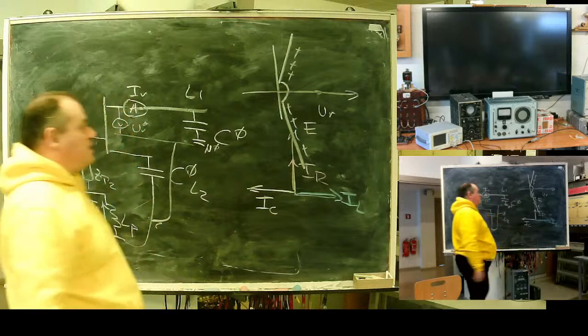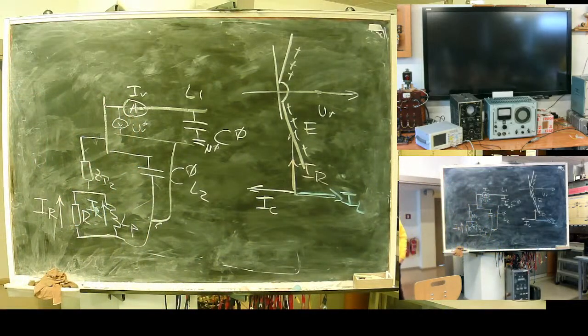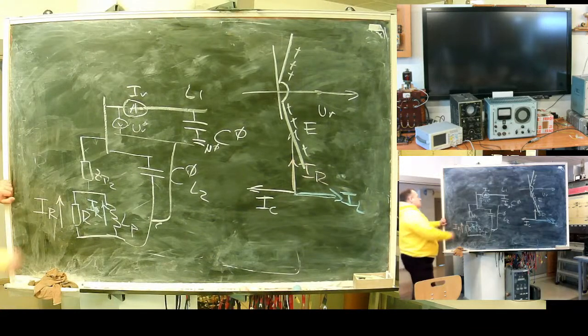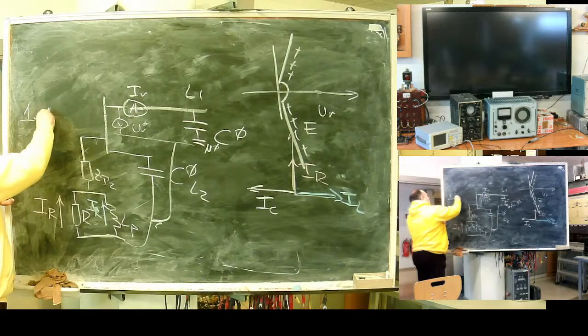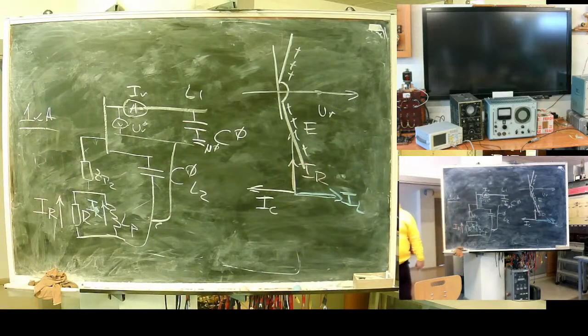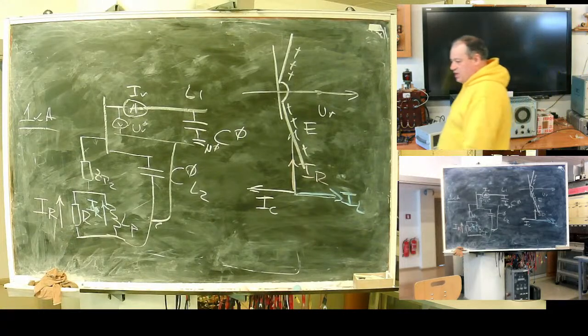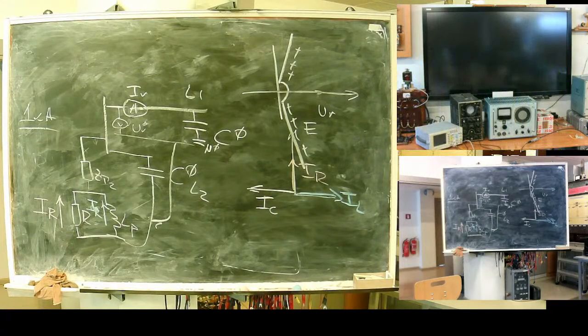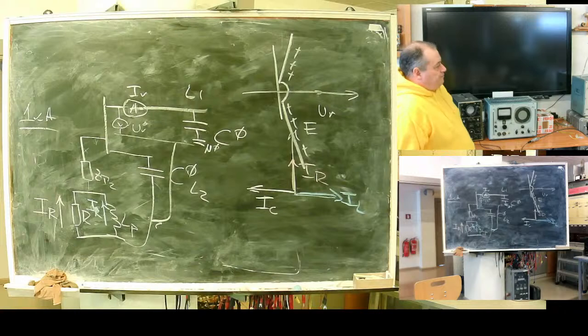Here is your characteristic. It will work here in Riga. This current is set to 1 kiloampere. We have this in our city network, we have this schematic. It's called low ohm neutral. Not isolated, not compensated, but low ohm neutral. That's what we got here.